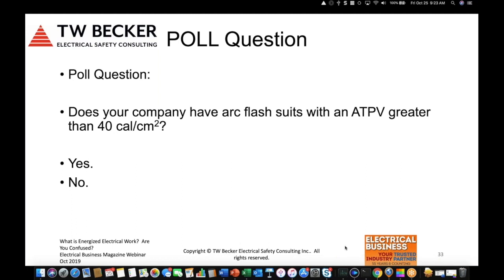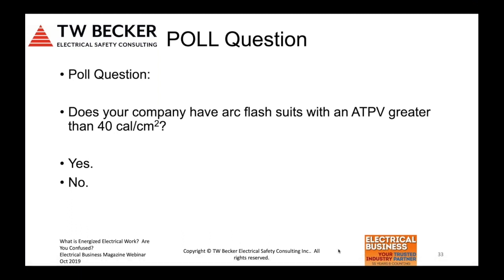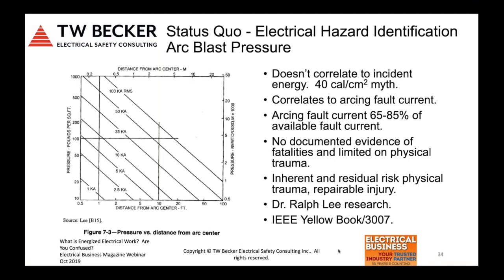That poll question was strategic with respect to some of the information I'm going to present later about the myths and misinformation about doing energized electrical work. So arc blast pressure, just a slide if you haven't seen this before, because when I do show this, people will have never seen this graph before. Arc blast pressure correlates to arcing fault current, not incident energy. So this is what I call the 40 calories per centimeter squared myth, that work has to stop because it's dangerous or the risk is too high due to blast pressure, which is again completely wrong.